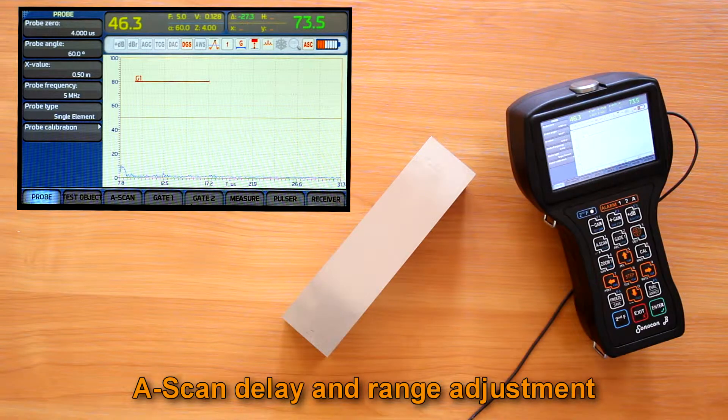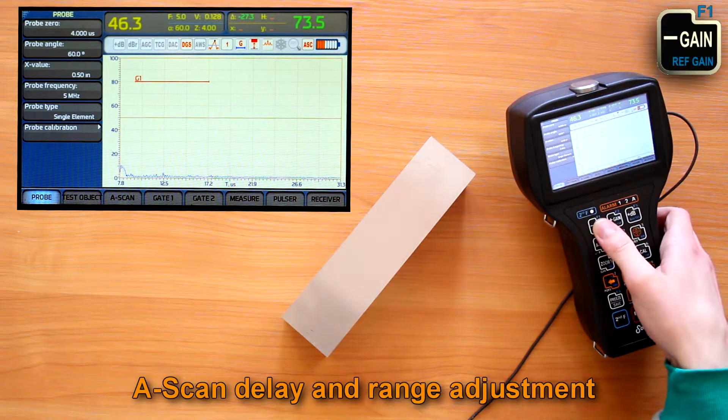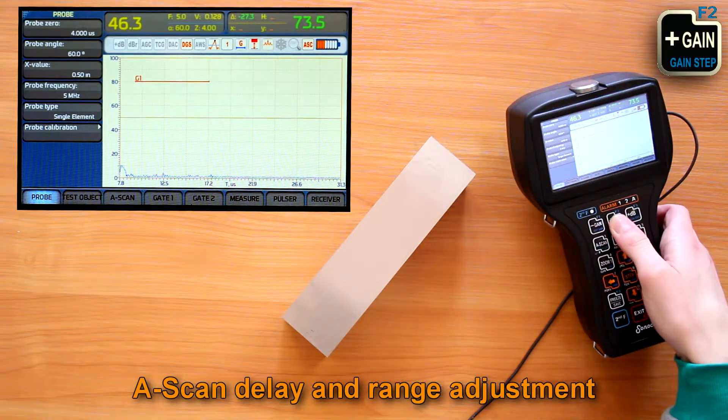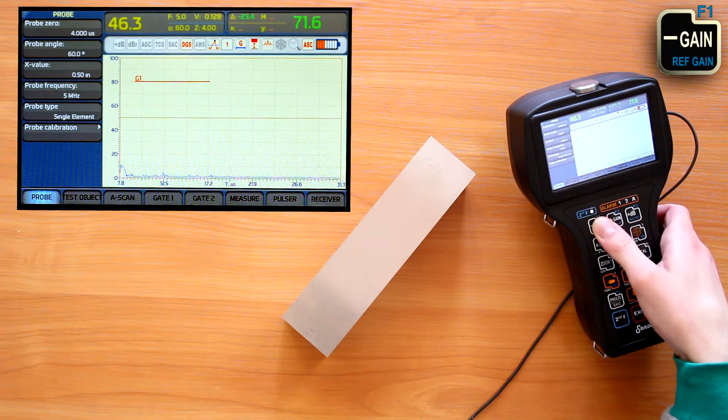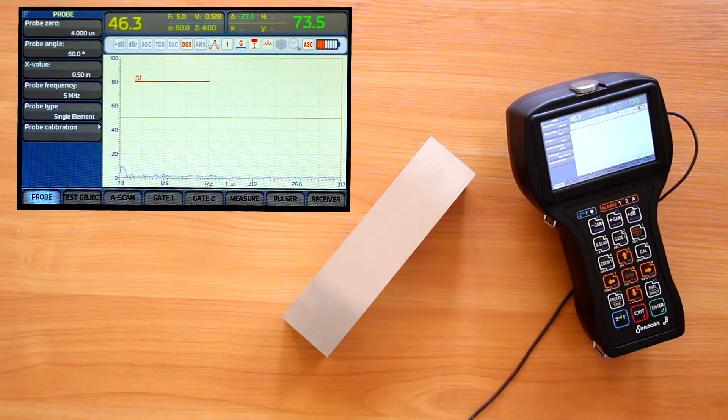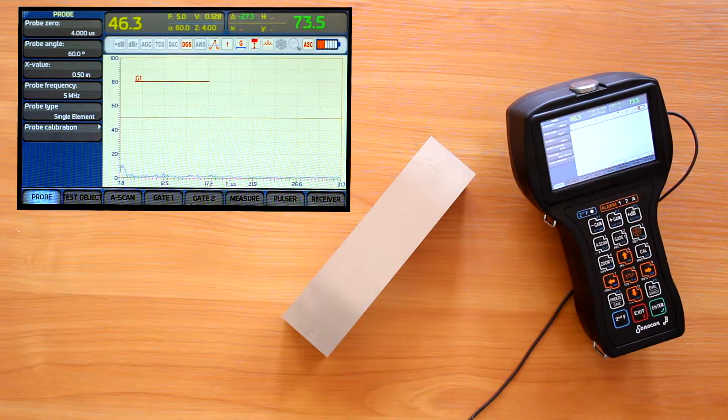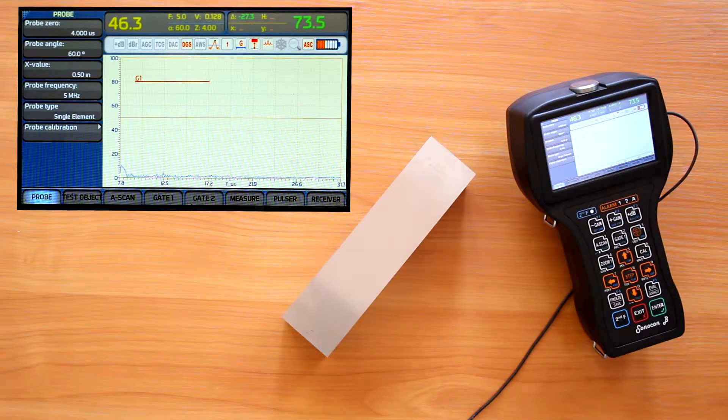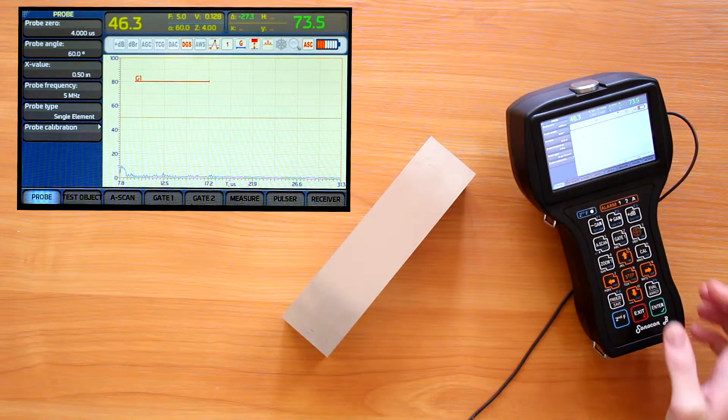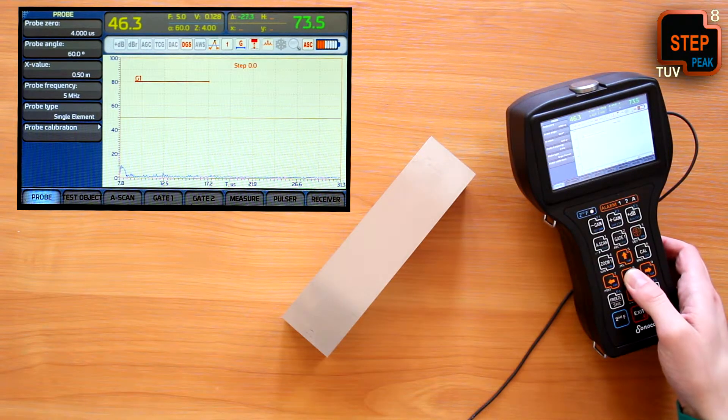We can increase or decrease A-scan range with gain plus and gain minus buttons. When changing one of the A-scan parameters, the step button cycles its increment-decrement step.